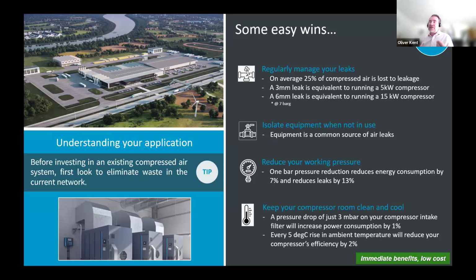And when we look at how much air is lost through leakage, working at 7 bar, which is a typical compressed air system working pressure, a 3 millimeter leak is the equivalent of running a 5 kilowatt compressor day in, day out. A 6 millimeter leak, still not a very large hole, is the equivalent of running a 15 kilowatt compressor day in, day out without any benefit to your production.